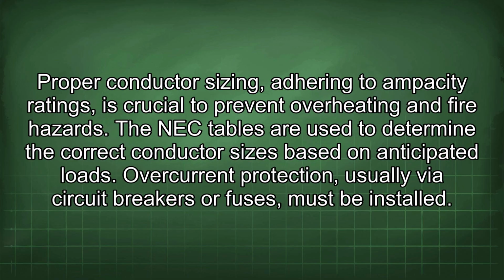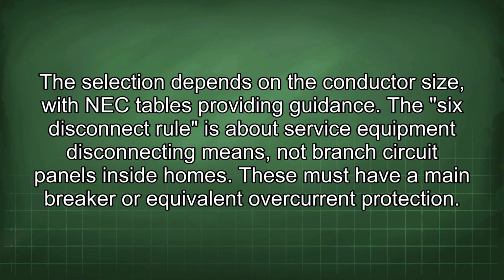Proper conductor sizing, adhering to ampacity ratings, is crucial to prevent overheating and fire hazards. The NEC tables are used to determine the correct conductor sizes based on anticipated loads. Overcurrent protection, usually via circuit breakers or fuses, must be installed. The selection depends on the conductor size, with NEC tables providing guidance. The 6 disconnect rule is about service equipment disconnecting means, not branch circuit panels inside homes. These must have a main breaker or equivalent overcurrent protection.